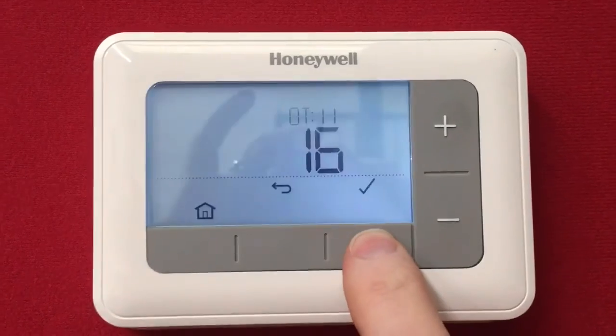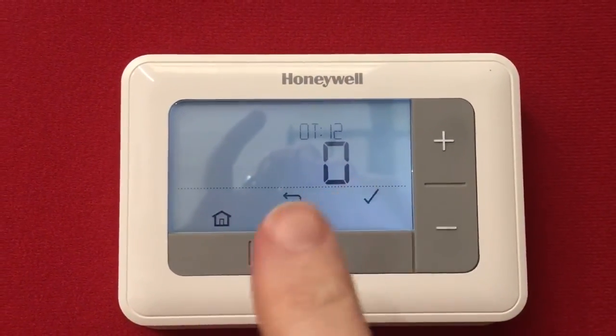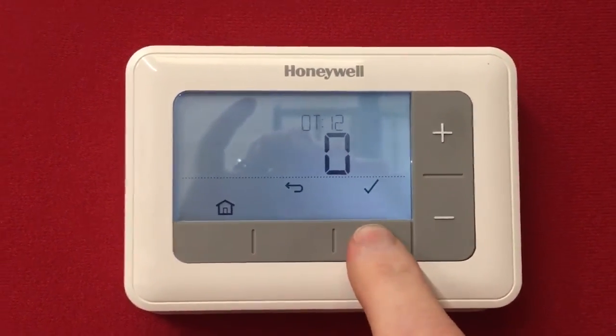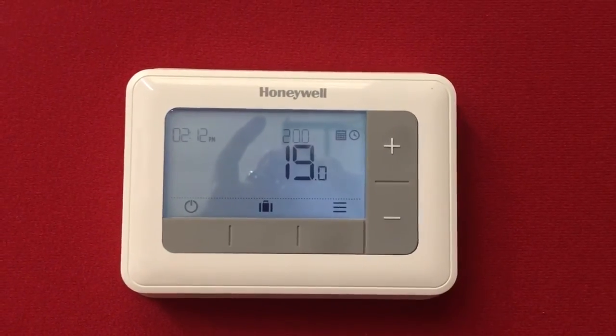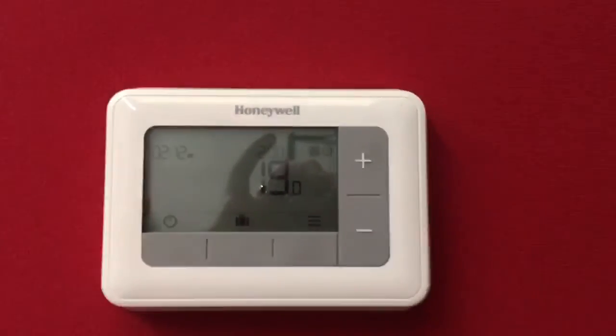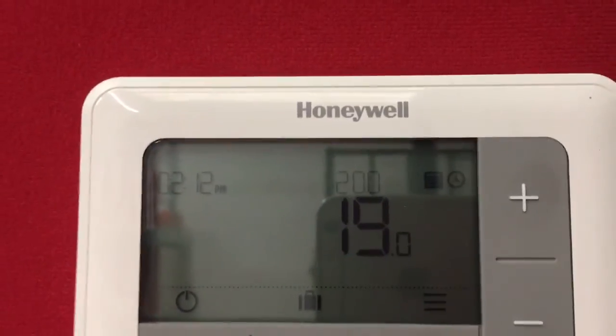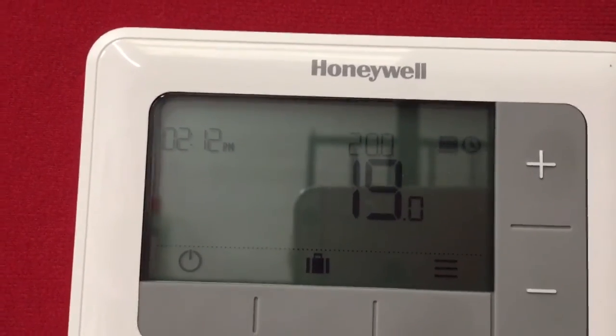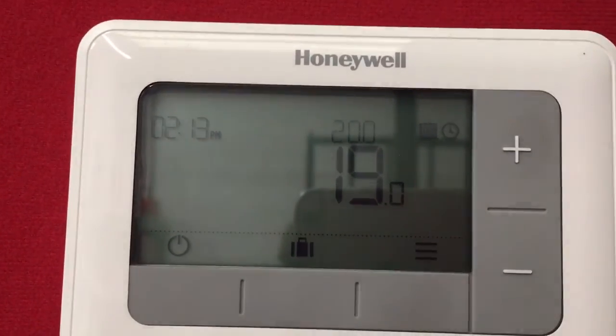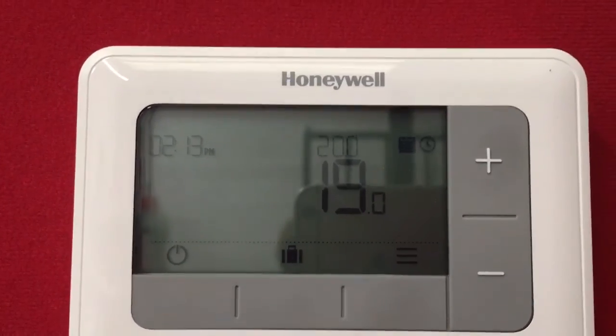Okay, so up here, so we've got the curve set to 16, just for the purpose of the video. We've got the room compensation actually turned off, okay? And if we save the settings like that, that's how the settings were before. So what you can see on the screen is that we've got a set point of 20 degrees, which like the curve is defined by the set point. So 20 degrees set point, 19 degrees is the actual room temperature in here at the moment.